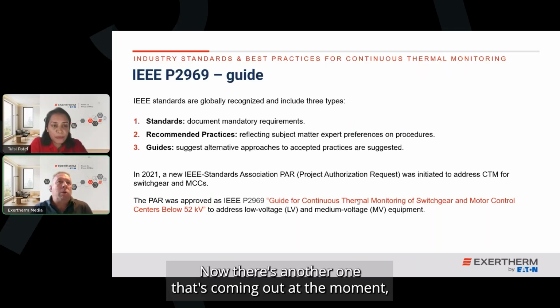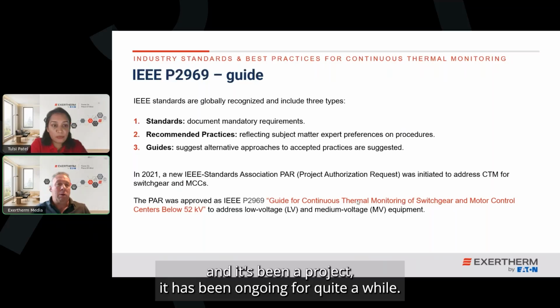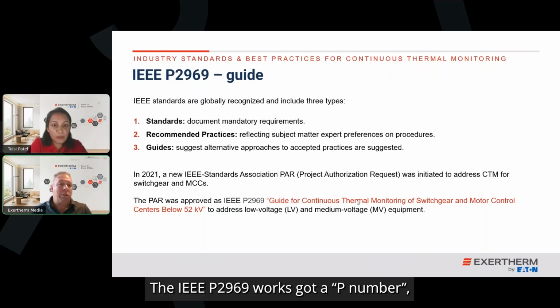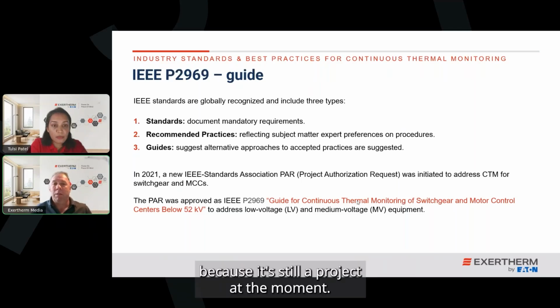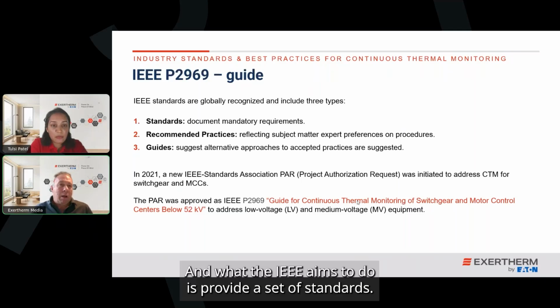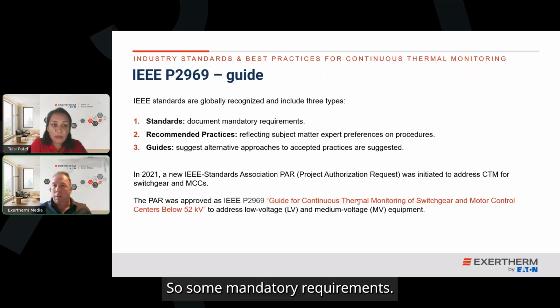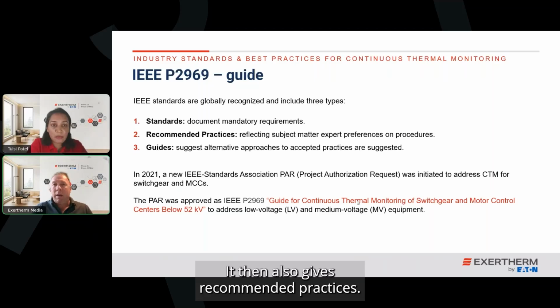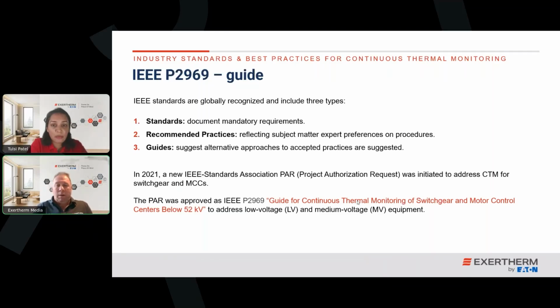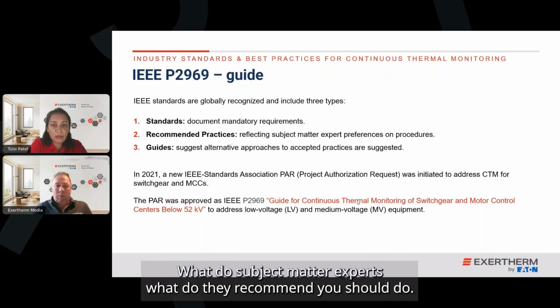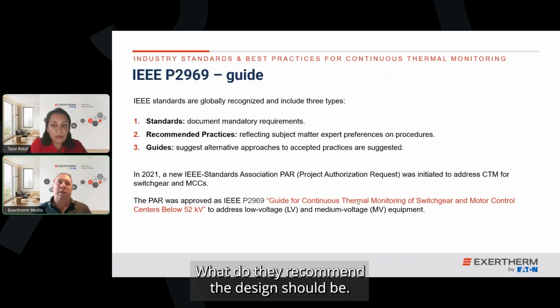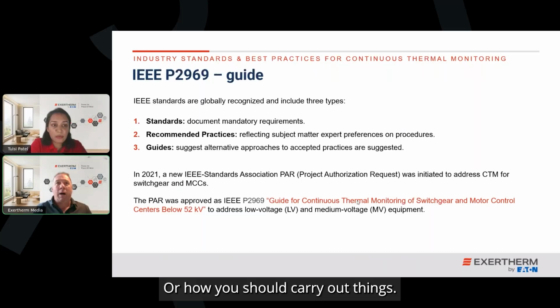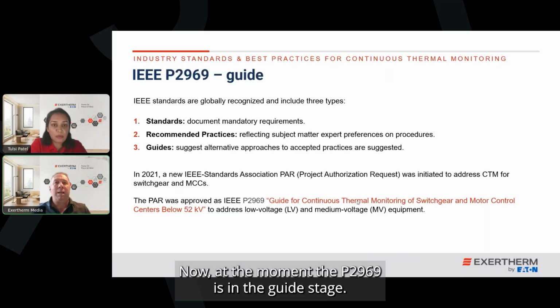Now, there's another one that's coming out at the moment, and it's been a project that's been ongoing for quite a while, the IEEE P2969. It's why it's got a P number, because it's still a project at the moment. What the IEEE aims to do is provide a set of standards, so some mandatory requirements. It then also gives recommended practices. So what do subject matter experts recommend you should do? What do they recommend the design should be? What do they recommend you should put in there, or how you should carry out things? And then guides, which are just suggested approaches. Now, at the moment, the P2969 is in the guide stage.